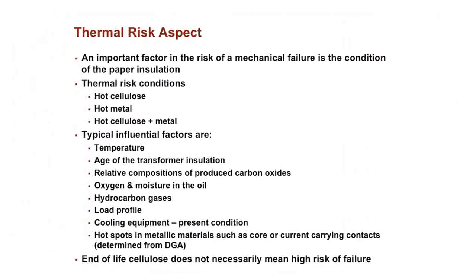If it's between about a 3 to 10 ratio, that's normal aging. But if it's higher or lower, that indicates a different type of fault is going on. We look at the oxygen and moisture in the oil. If you have a lot of oxygen or a lot of moisture, of course, then the cellulose ages much faster.